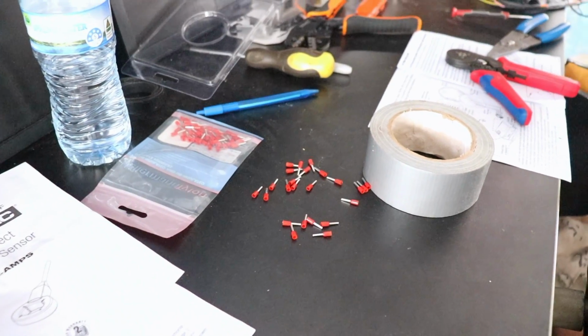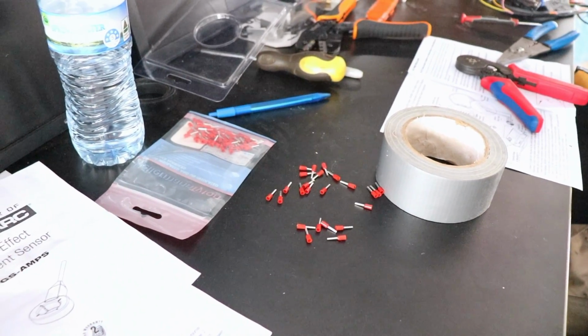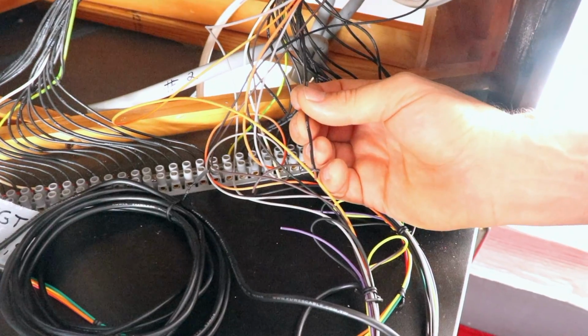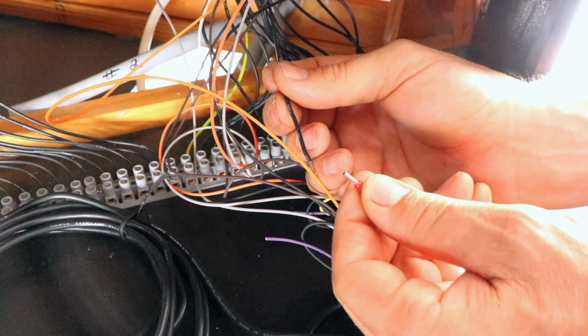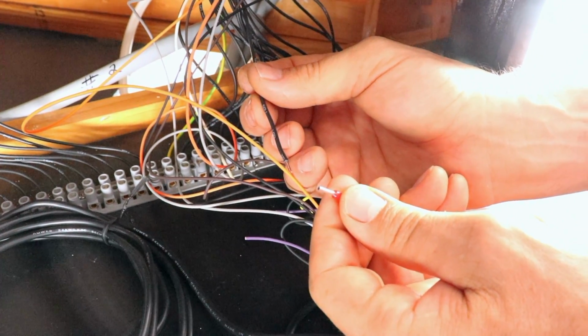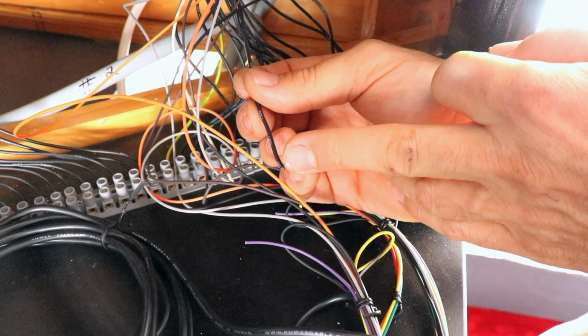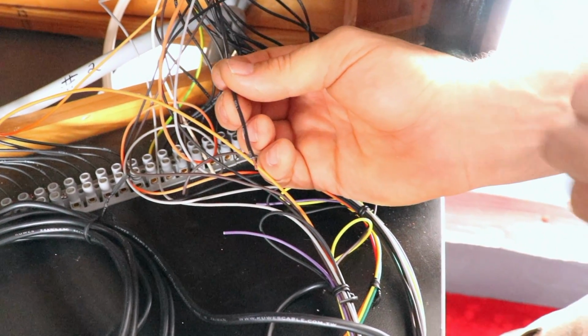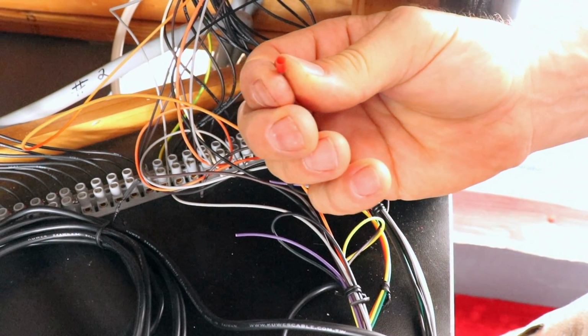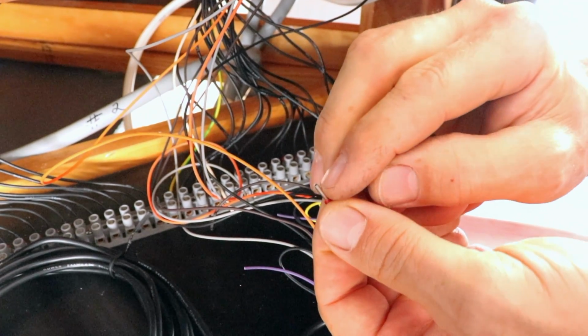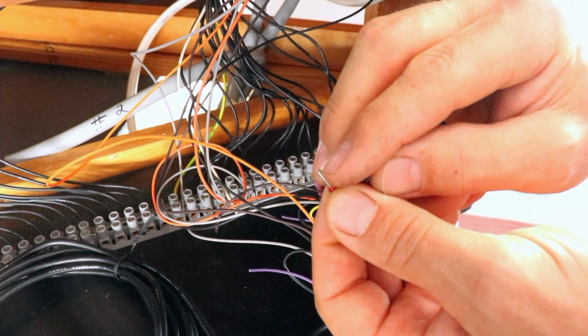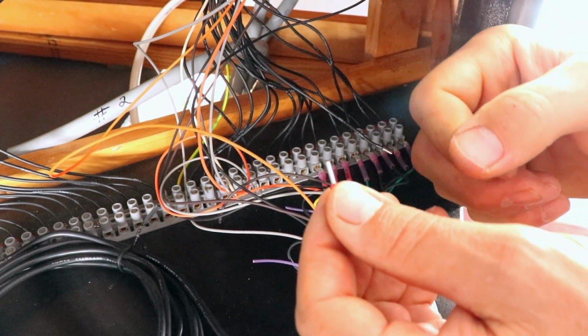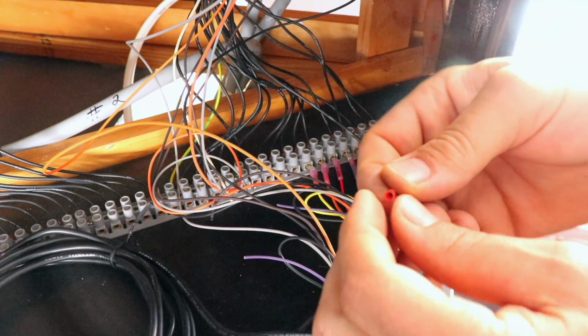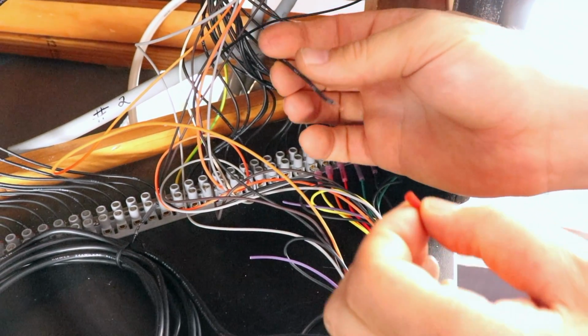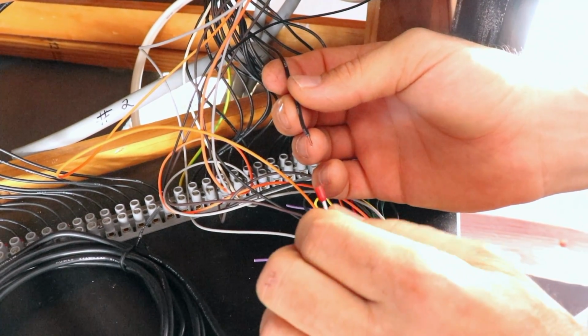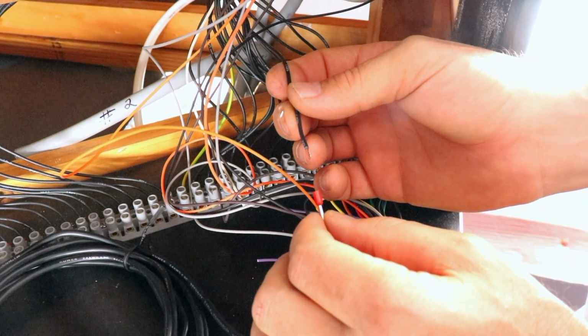We don't want that as a point of resistance, and therefore a point of moisture and failure going forward. So when you're stripping the wire, you want it stripped the length of the piece you're fitting, so the back of the insulation butts to the back of this and protrudes to the front. When you crimp, everything gets crimped, and the shielding actually helps strengthen the copper, if that makes sense.